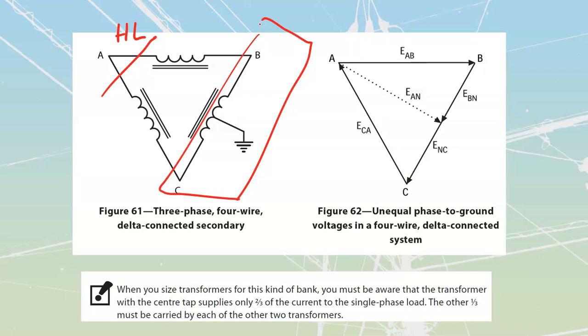It's uncommon to have one of these transformer connections because they're a difficult transformer to obtain. It is far more common that if you have a delta type of system, you're just going to use the delta transformer to supply your three-phase loads, and then you'll just grab a single phase transformer. You'd be able to get a 240 center tap transformer. Actually, it would just be an auto transformer that you would tap across that, and then you would be able to create a neutral from that one.